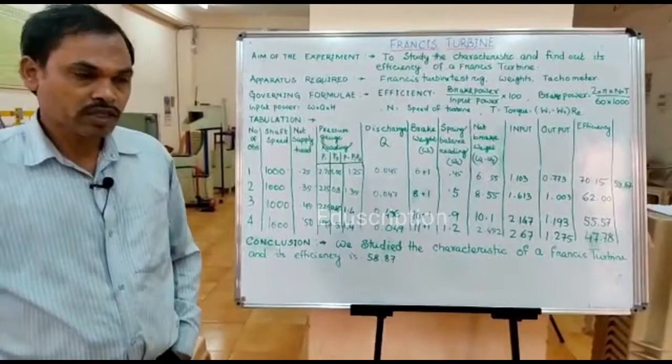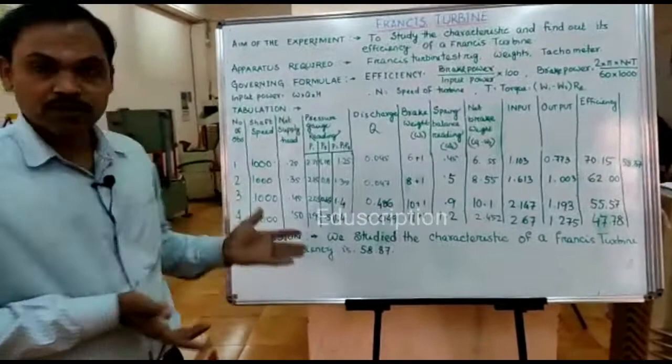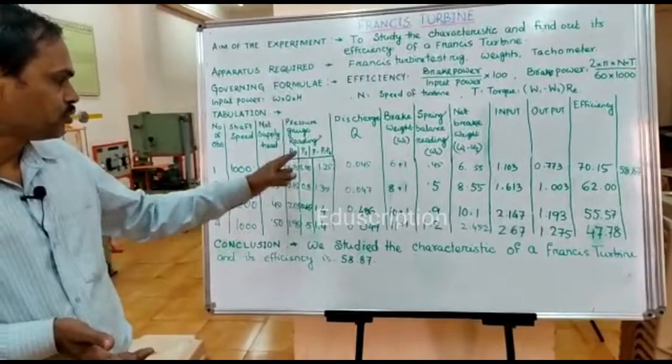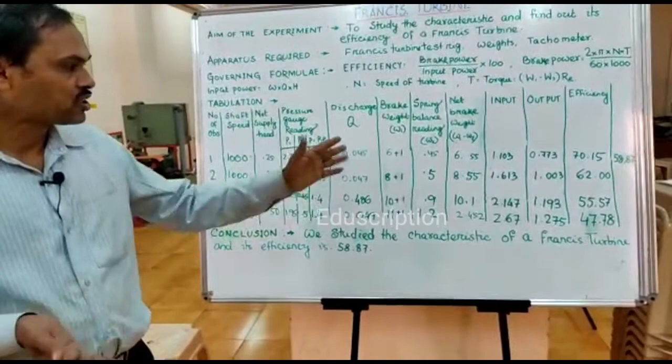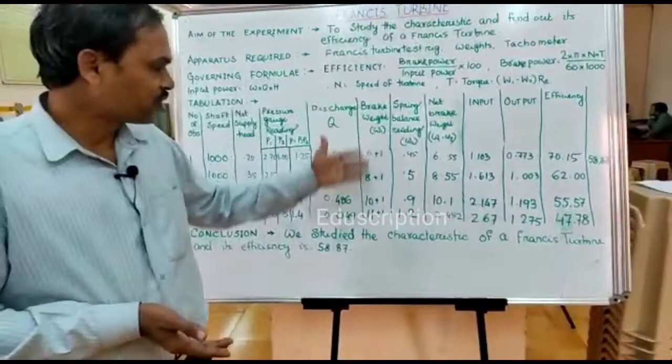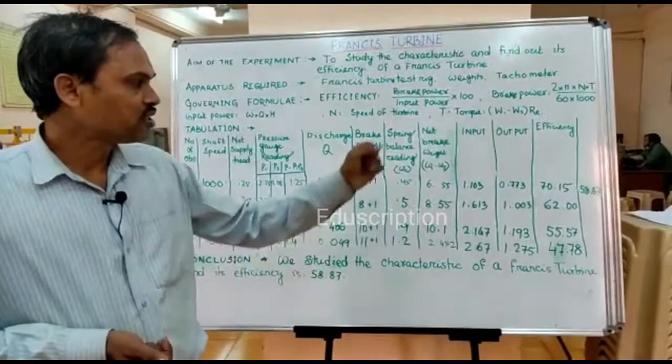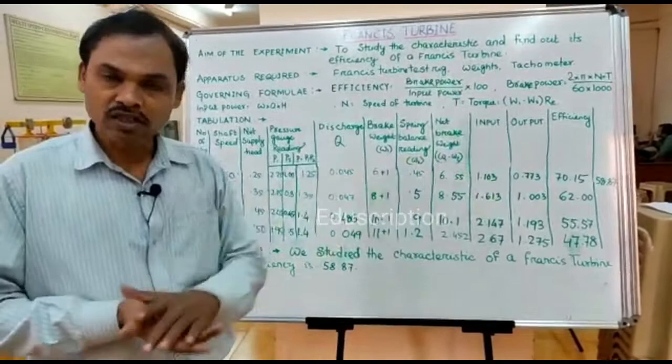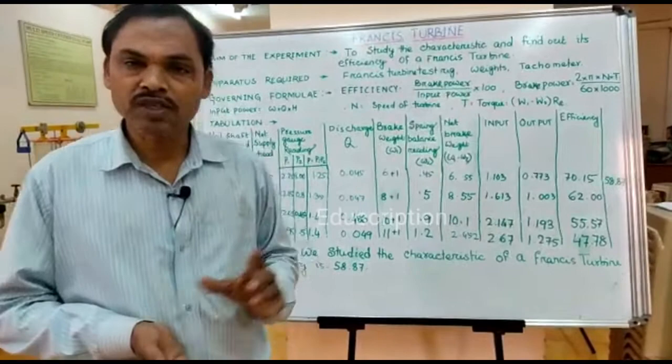Next we move to the tabulation part. We are taking 4 observations recording P1 and P2, inlet pressure and throat pressure, discharge, the brake weights, and spring balance readings, finally computing input power, output power, and efficiency. In the conclusion part, we studied the different parts and functions of the Francis turbine and found its efficiency to be 58.87 percent.